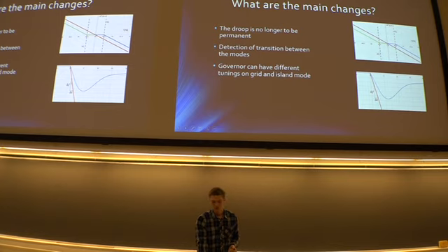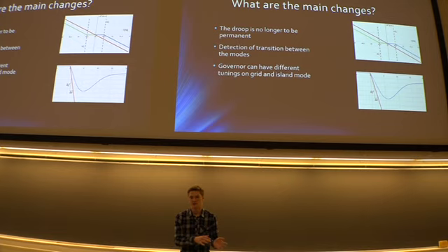Also, you want to introduce the rate of change of frequency, which is a measurement of how unstable the system is. If this frequency drops below this red line, it must go into island mode, because then it's not the stable system as the grid is anymore. Which means that it can go over to a set of more stable PID parameters, which is predetermined in the governor.